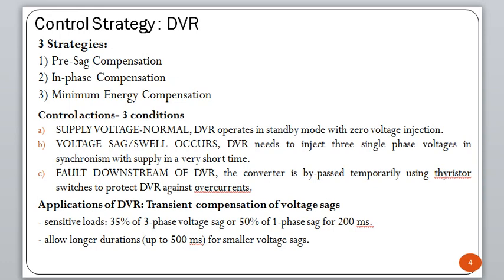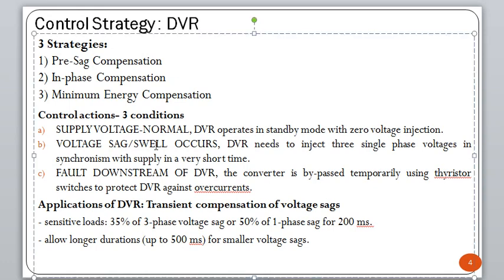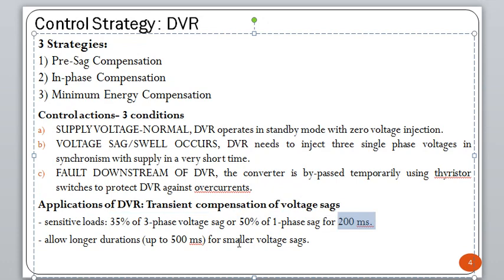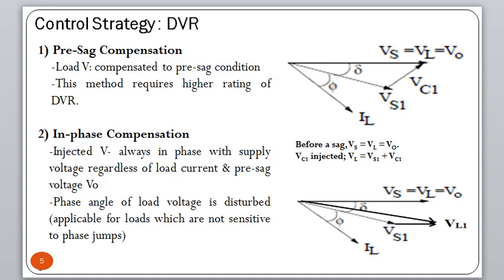DVR applications: it works for sensitive loads, protecting them. It can compensate up to 35% three-phase voltage sag, and up to 50% single-phase voltage sag for a duration of 200 milliseconds. If the voltage sag is less than 35% but compensation is needed for a longer duration (e.g., 500 ms), it can compensate for that longer duration as well.